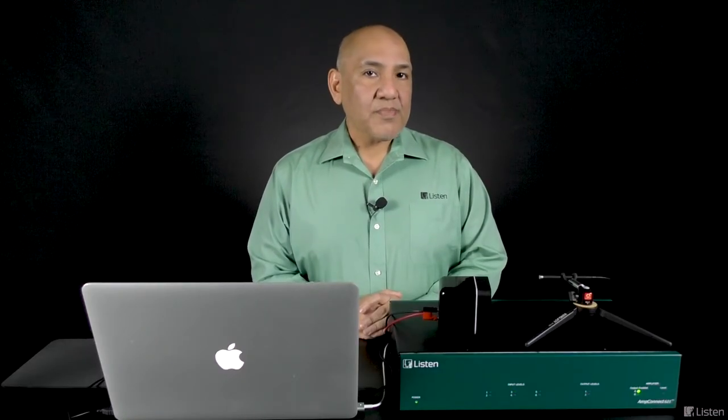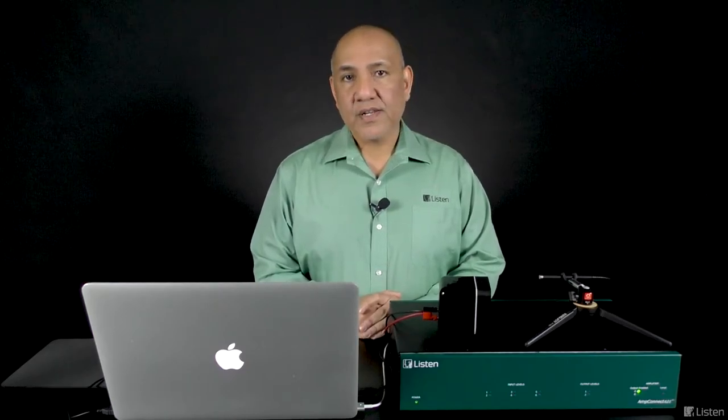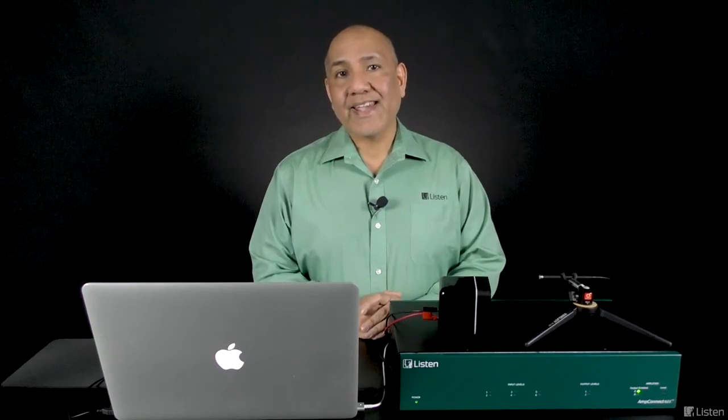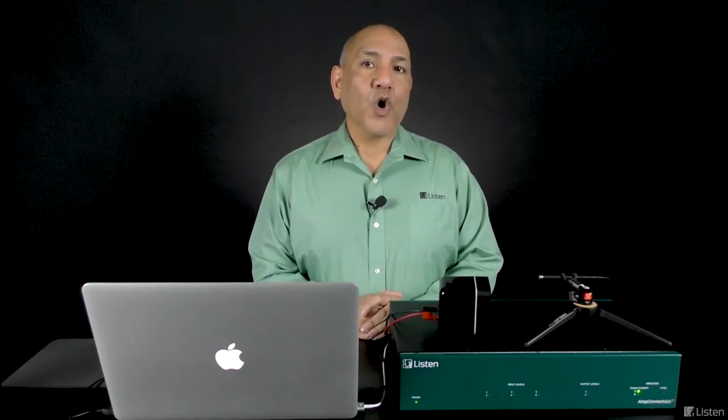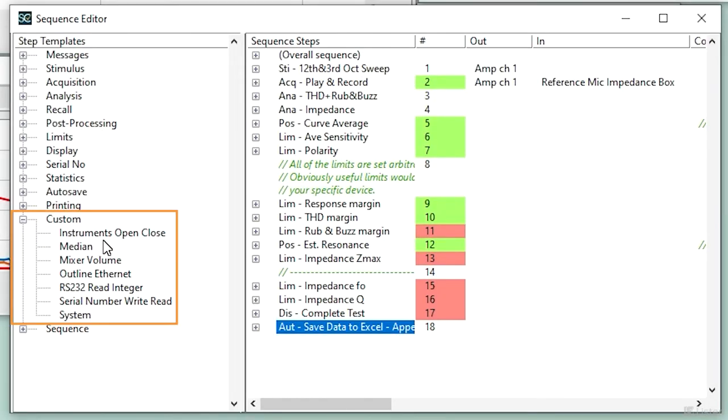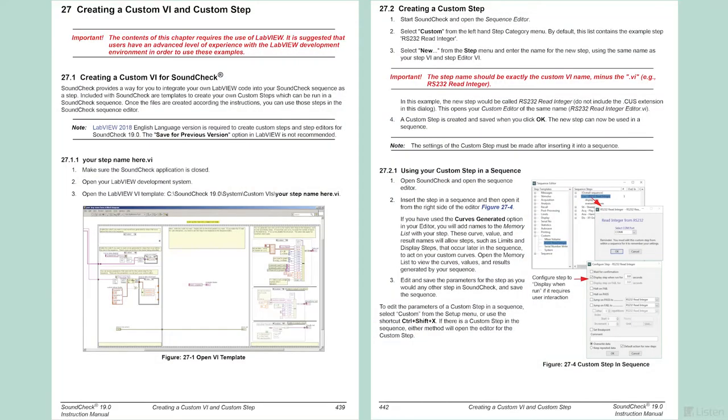SoundCheck's custom step is yet another powerful way to customize your test sequences for the production line. Custom steps are executed like any other step in SoundCheck. However, you have full control of what this step can do. There are two ways the custom step can be used. One, develop your own LabVIEW custom VI, which can be run as a step in SoundCheck. Here are a few that we created. Your own LabVIEW custom VI can populate this list. The SoundCheck user's manual provides full documentation on how to link your LabVIEW custom VI as a custom step in SoundCheck.